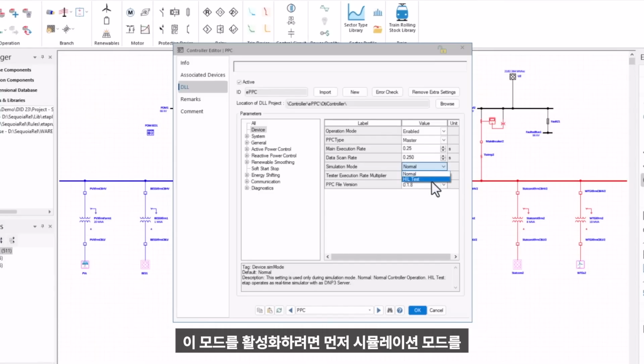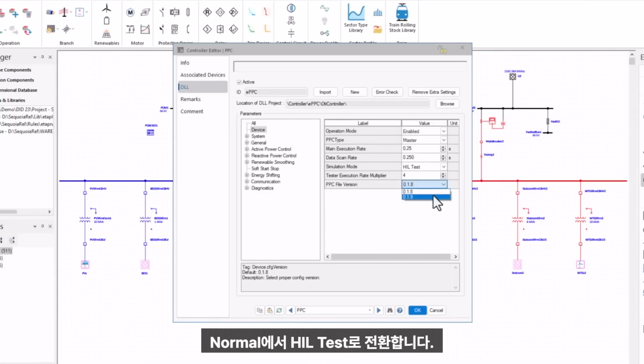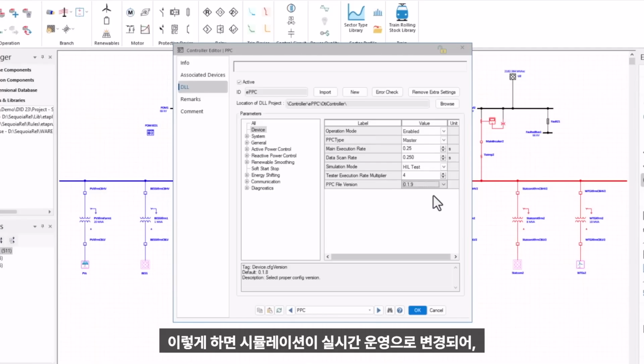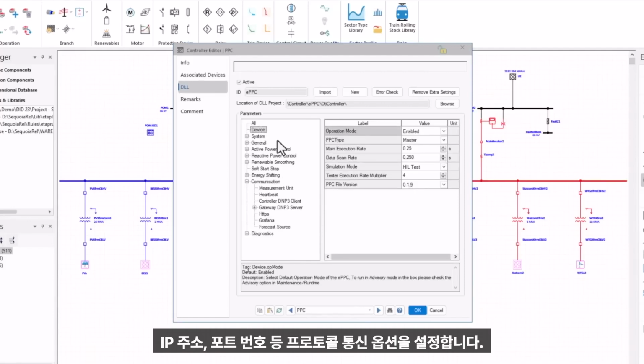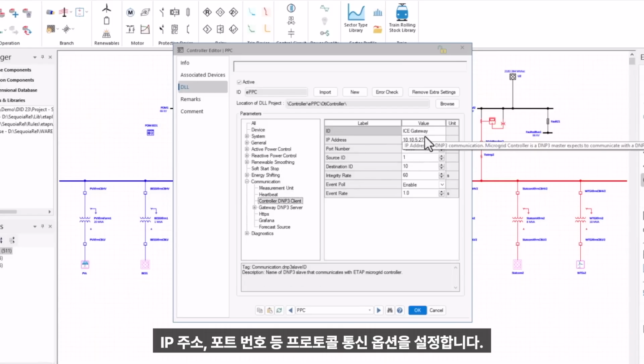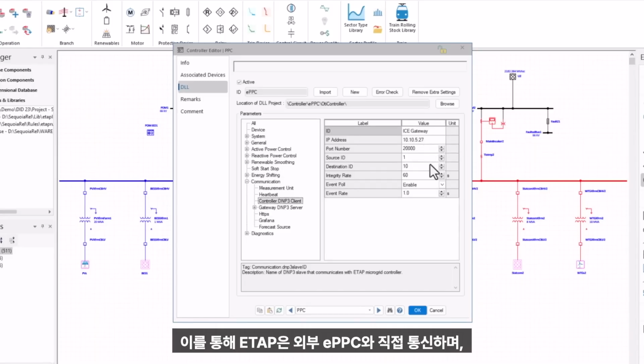To enable this mode, we first switch the simulation mode from normal to HIL test. This changes the simulation into real-time operation, so data is processed and exchanged at the same pace as it would be in an actual plant. The next step is to configure the DNP3 communication settings, including parameters such as the IP address, port number, and other communication options required for the protocol. This allows ETAP to communicate directly with the external ePPC hardware and exchange real-time data just as it would in a live deployment. Once the HIL configuration is complete, we can deploy the control logic.